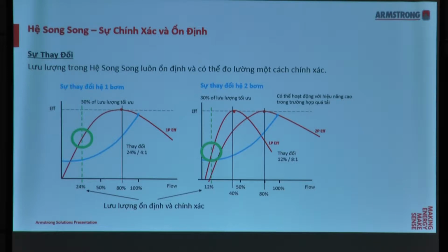Next, when it comes to turn down, so turn down is basically good for applications like your boilers and your variable flow applications. So here for one pump turn down to lower flow rates, it's a 4:1 turn down ratio, to 30% of your BEP. It's at 24%. And when you have 2 pumps turned down, what you're able to achieve is an 8:1 ratio, at 12% of your design flow. So this is again what turn down is: turn down is the percentage of design flow at which the flow becomes stable and is able to be accurately measured.